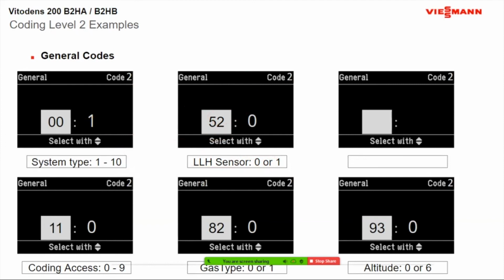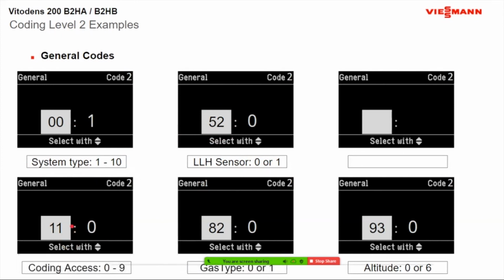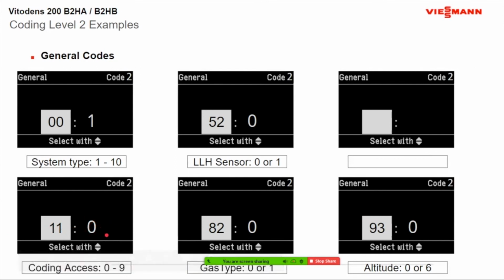When you're changing your gas coding from natural gas to propane, there is a coding that you have to go into, address 11. The password for that address 11 is 9. Once you hit OK with 11, the 0 now comes highlighted. You hit your up arrow till 9 comes in there, and that will allow you to go to address 82.